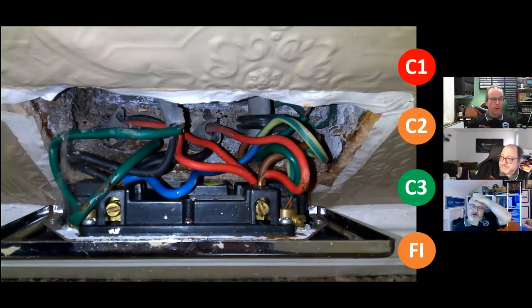Do you know what? One of the things I like to do, and I know, Dave, you think it's quite good, is I like to tie these into EAWR as well. So just on this, I could probably argue Regulation 5 and 7. You know, insulation, protection and placing of conductors. So it would be covered, protected to prevent danger. I don't think that connection is in compliance with EAWR Regulation 7, to be perfectly frank. I'm sure somebody will probably argue with me. And strength and capability of electrical equipment.